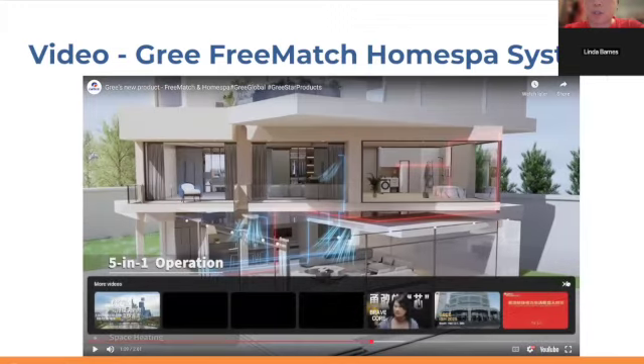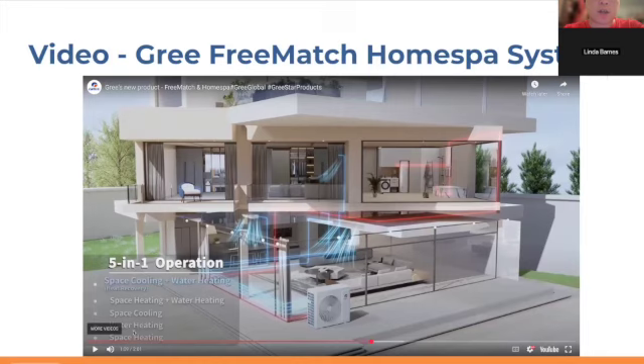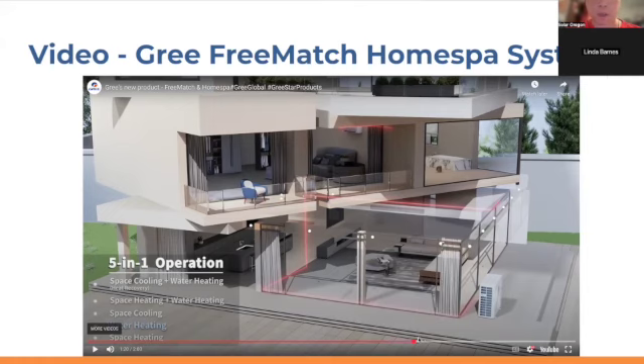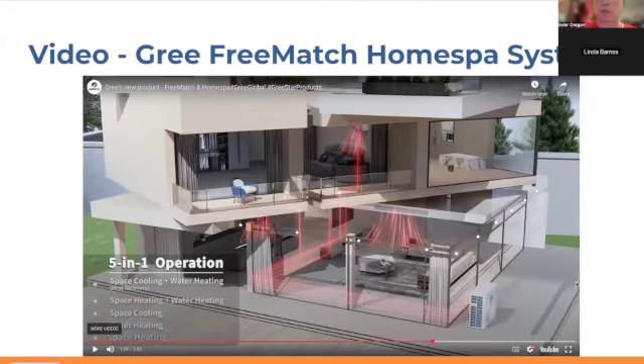Okay, so we're going to pause the video in this area to show you what's going on in these different modes when it comes to combi heat pumps, because this is the unique part of combi heat pumps. It can do space cooling and water heating at the same time in some systems. Like this one's a refrigerant split system that pipes the refrigerant all the way to each end product, so the refrigerant goes all the way to the water heater tank, and it can also do just space heating. And so those are the different modes.